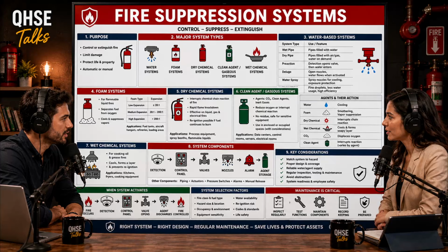But I've read that once the equipment is de-energized, like say you flip the main breaker to that panel, the fire is technically no longer a Class C fire. Is that true? That is correct from a strict classification standpoint. Electricity itself doesn't burn. What's burning is the plastic insulation around the wires. Right, the fuel. So once the power is definitively cut, it reverts to a Class A or Class B fire. However, during the chaotic, incipient stage of a fire, it is incredibly dangerous to assume the power is fully isolated. Because the breaker might have failed. Exactly. You always treat it as Class C until it's proven de-energized through proper lockout-tagout procedures. That makes total sense. You don't want to bet your life on a faulty breaker.